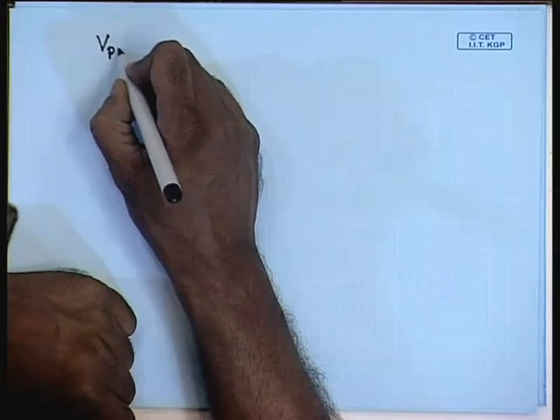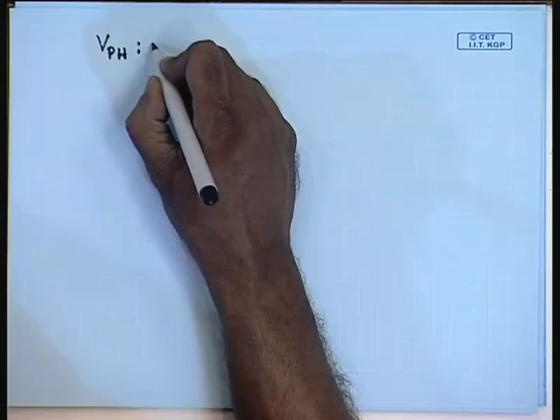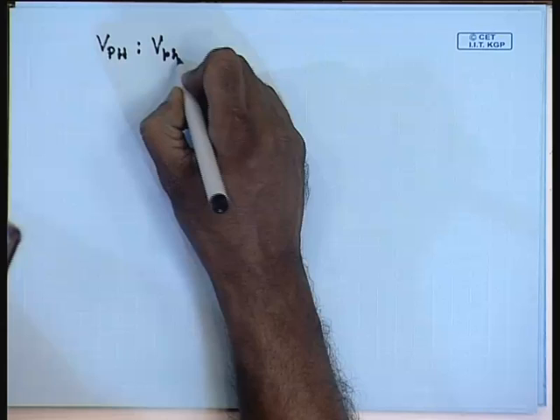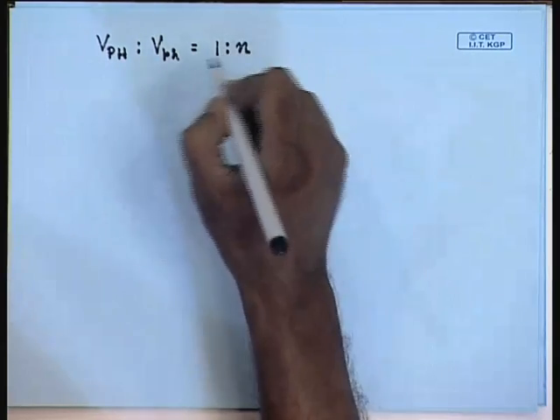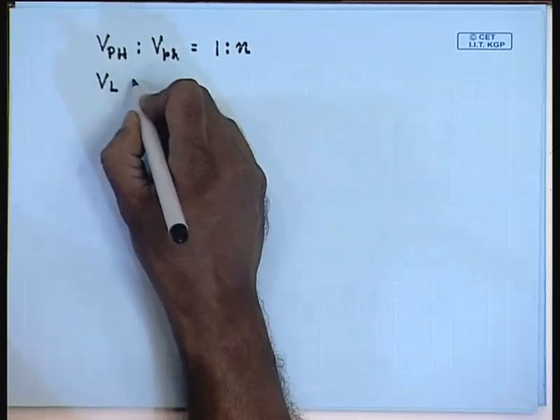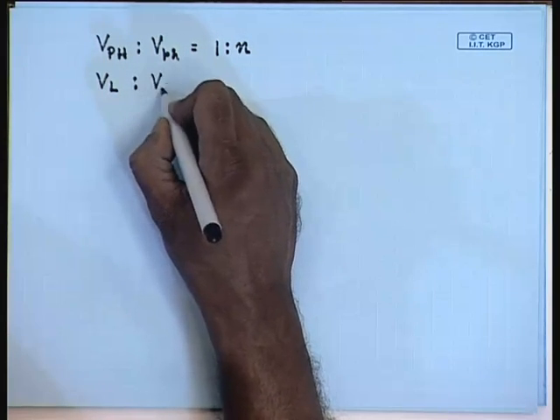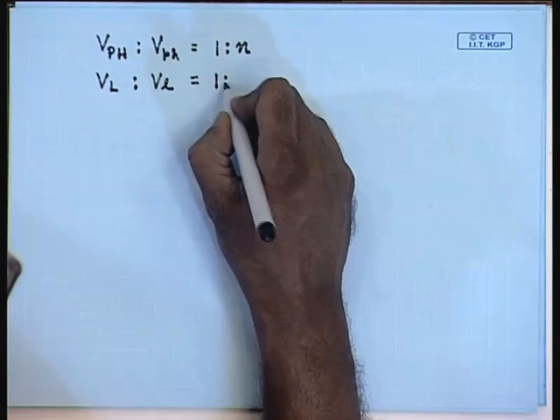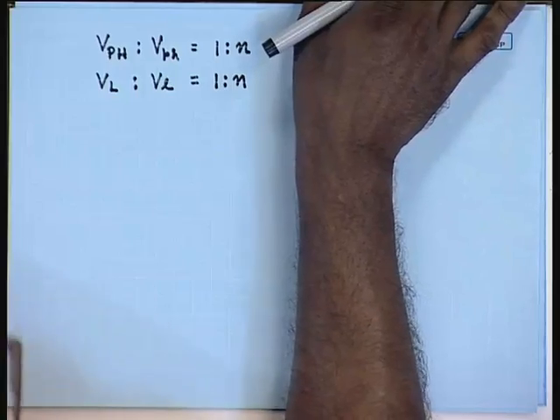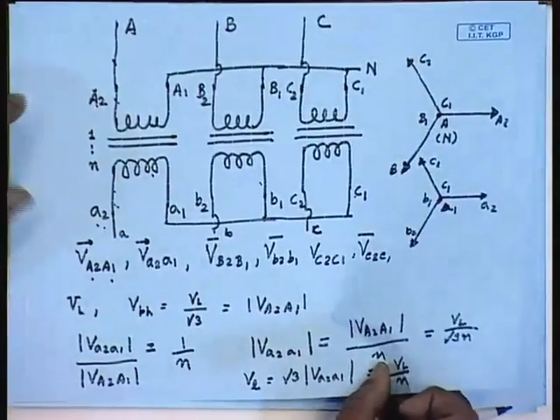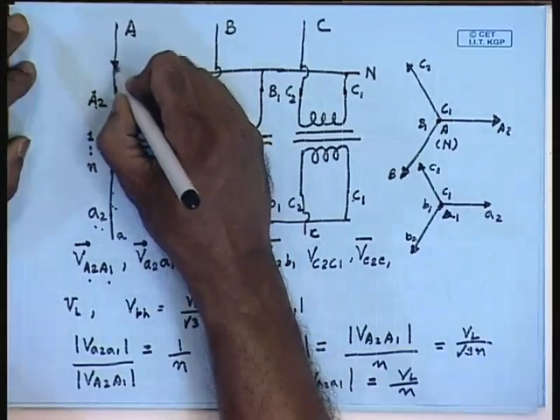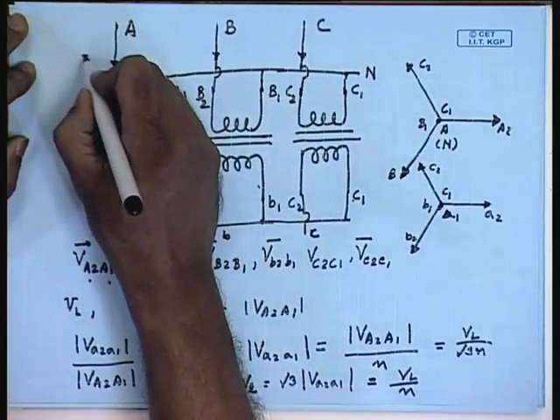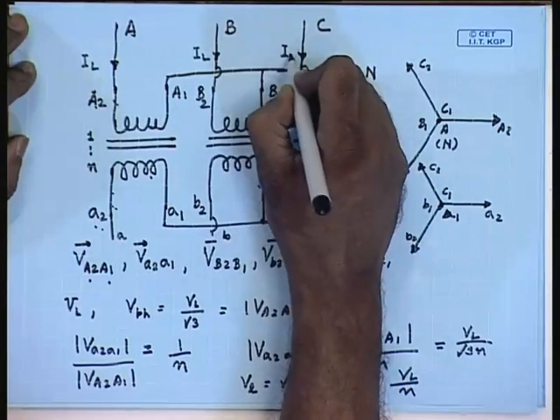So, the phase voltages in this case are related as high voltage side phase voltage to low voltage side phase voltage is 1:n, same as the turns ratio. Also, the same relation holds for the line voltage of the high voltage side and the line voltage of the low voltage side, which are also related by 1:n. How about the currents? Let us say the line currents on the high voltage side are I capital L and the line currents on the low voltage side are I small l.